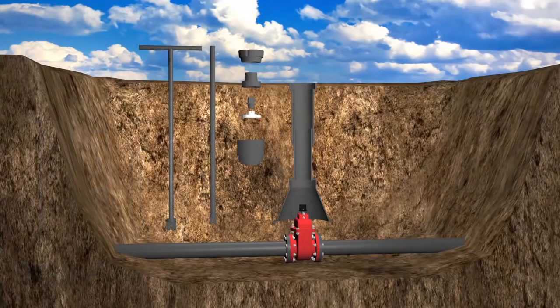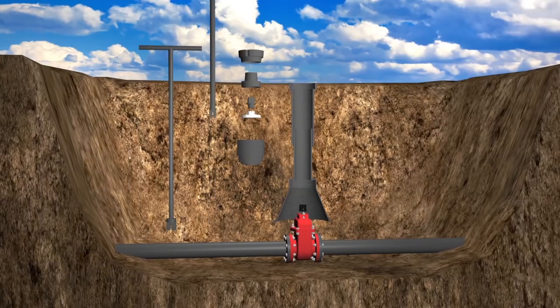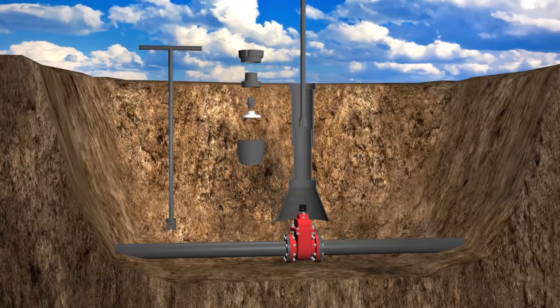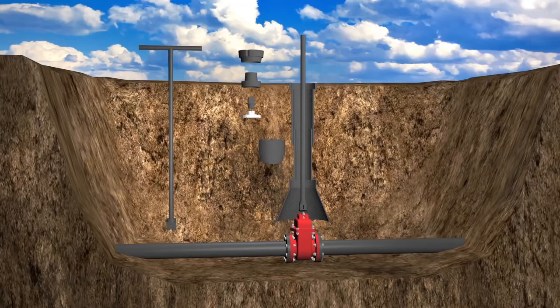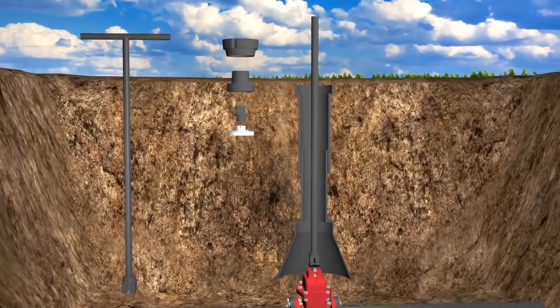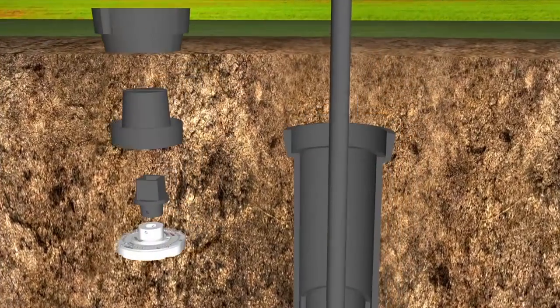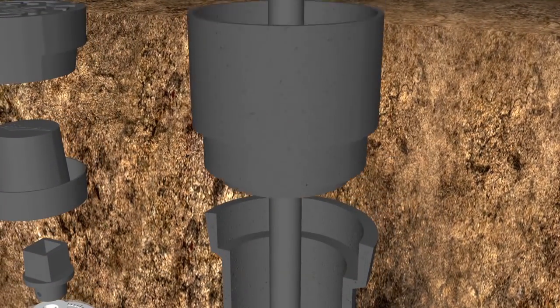With both valve and valve position indicator in the fully closed position, install the round extension stem onto the 2 inch operating nut of the valve. Place the cast iron housing adapter over the extension stem and into the valve box top section.